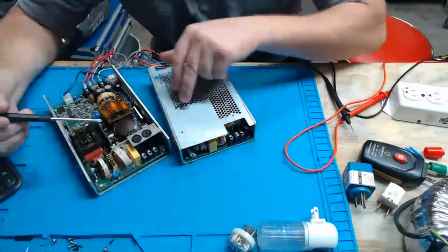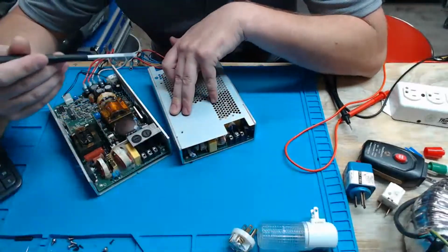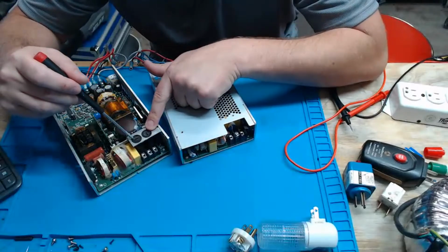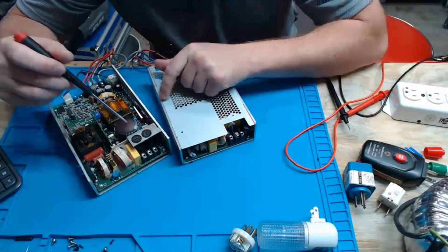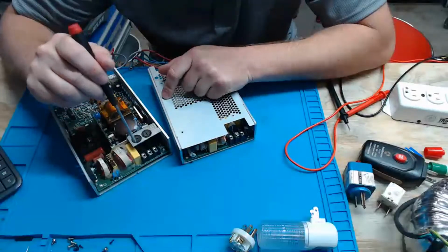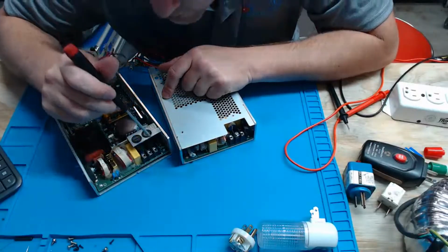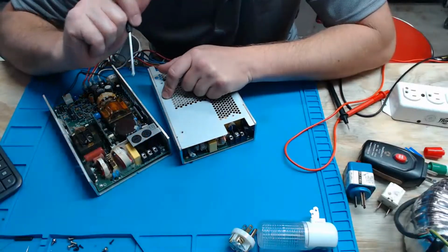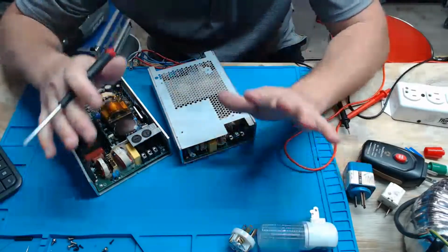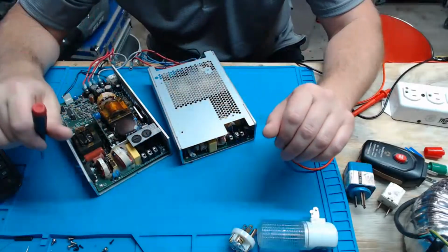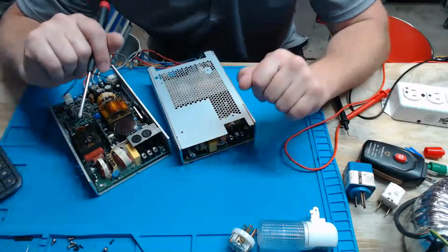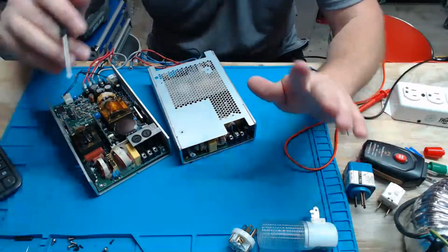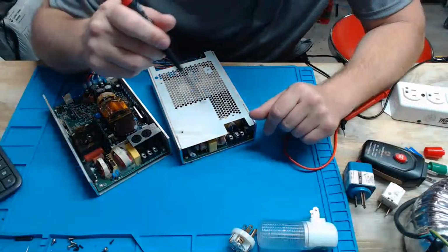Here is one of the major things that's going to stick out on a medical grade power supply. You see this right here? I have 2 fuses, and that is so convenient because one fuse is going to go to line and one of them is going to go to neutral. Both line and neutral are fused when it comes to a medical grade device. On most of them, anyway. I can't say that for all of them, but here in America, most of them.